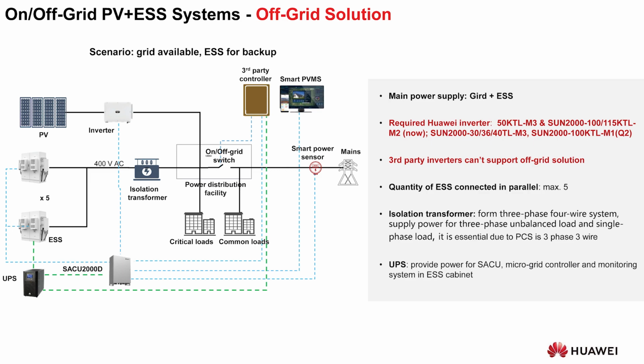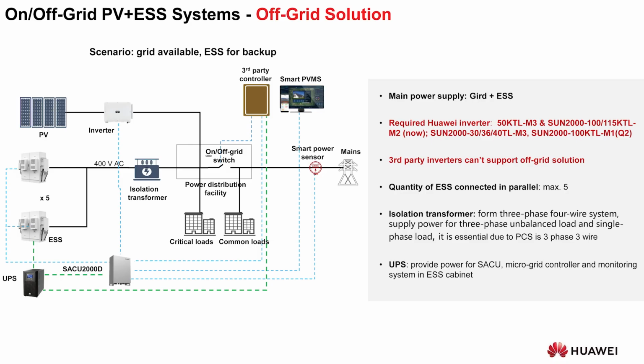So in this scenario, you're required to use the new inverters, which are the M3, V5 inverters, or the 100 kilowatt M1 or M2 version. Third-party inverters cannot be supported in this off-grid solution, okay? Quantity of the ESS connected in parallel is max of 5. The isolation transformer is there because it provides a 3-phase 4-wire system supply for a 3-phase unbalanced load and single-phase load. Due to the PCS being a 3-phase 3-wire system, we cannot provide for unbalanced loads. The PCS can only provide 33 kilowatts per phase. The isolation transformer will assist in providing for unbalanced loads as well, okay?